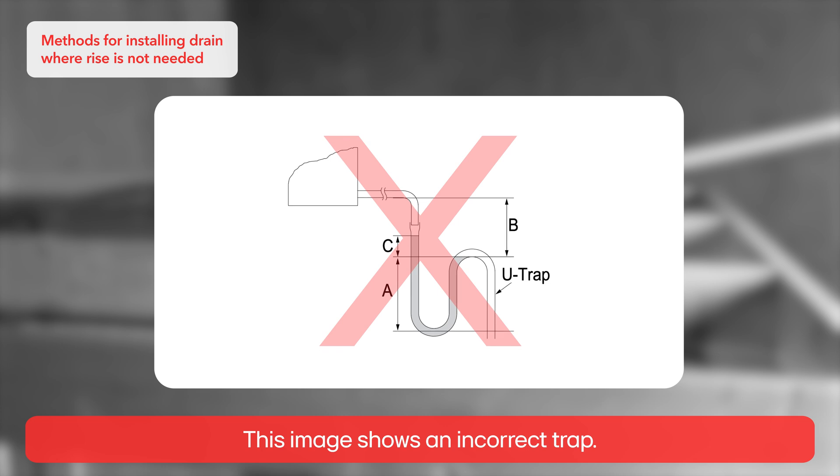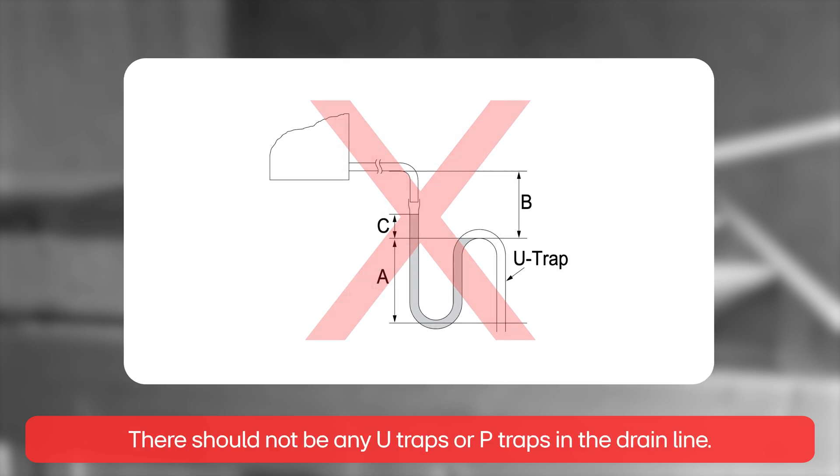This image shows an incorrect trap. There should not be any U-traps or P-traps in the drain line.